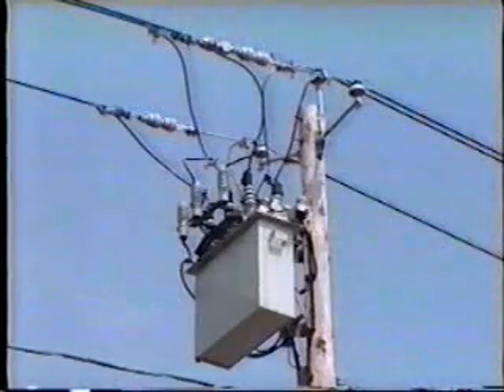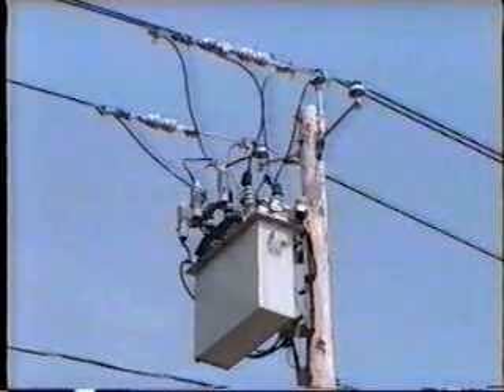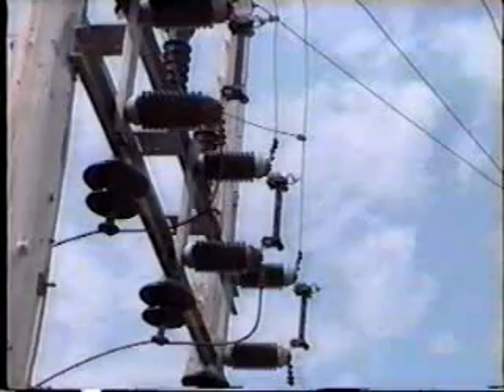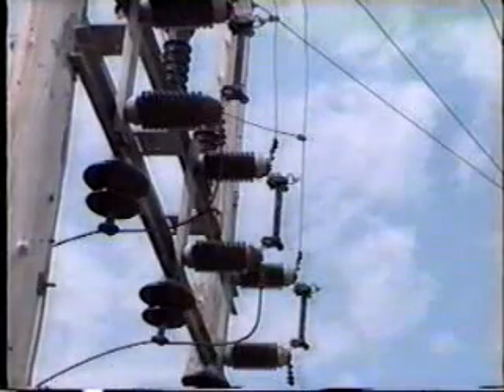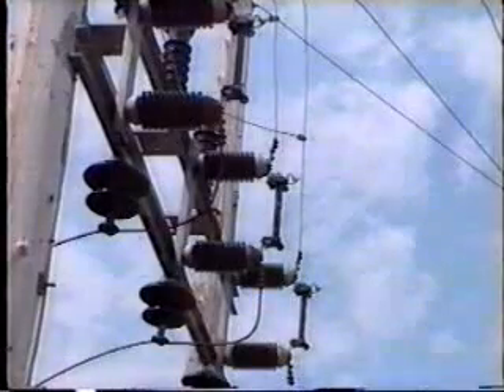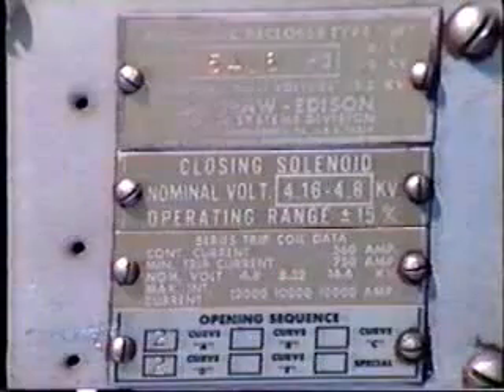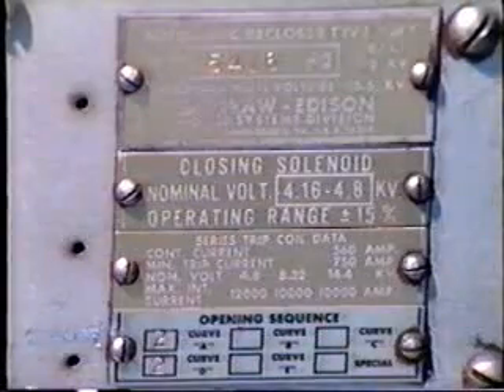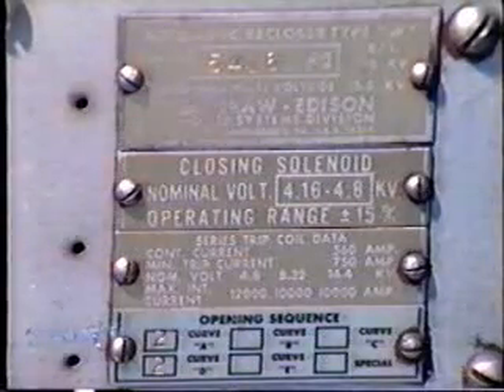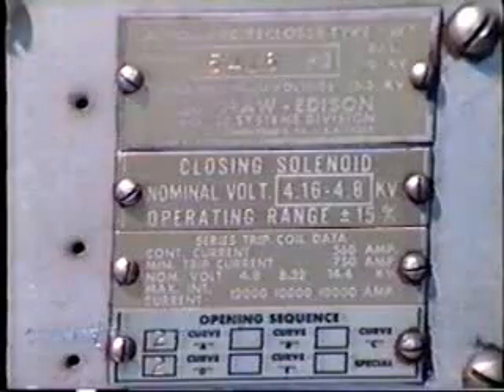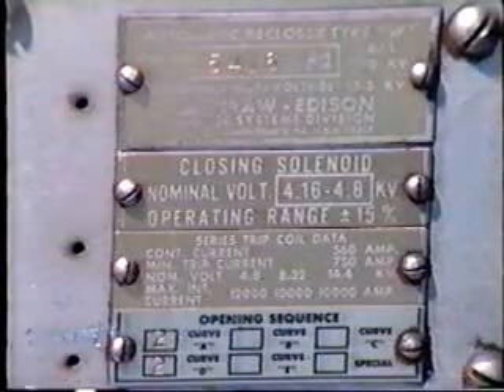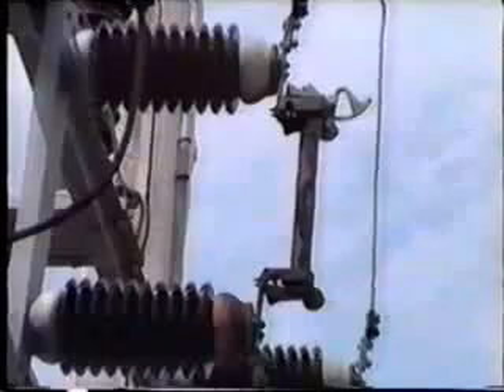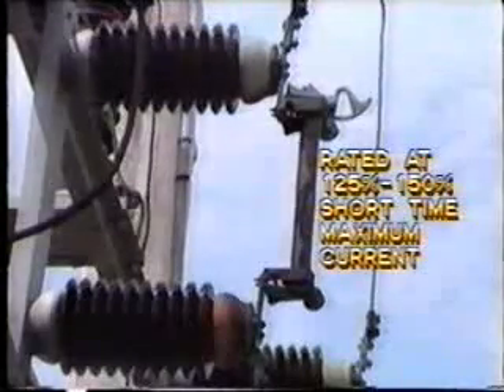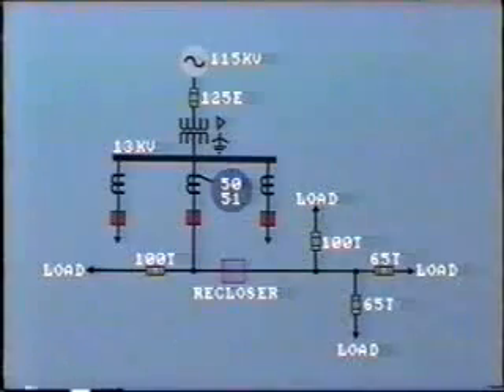In practice, other protective devices such as reclosers and fuses are usually installed along the line, and these are sized for the amount of current flowing in that part of the line. For example, the recloser usually has several settings. The first is instantaneous, one time only. The second and third settings have time delay. The fuse is usually rated at 125 to 150% of the short time maximum current. Let's look at an example.